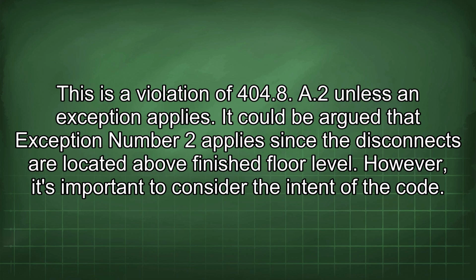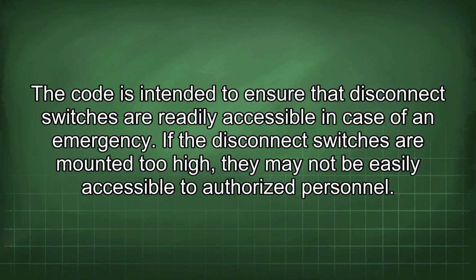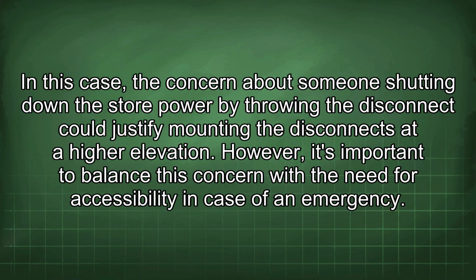However, it's important to consider the intent of the code. The code is intended to ensure that disconnect switches are readily accessible in case of an emergency. If the disconnect switches are mounted too high, they may not be easily accessible to authorized personnel. In this case, the concern about someone shutting down the store power by throwing the disconnect could justify mounting the disconnects at a higher elevation. However, it's important to balance this concern with the need for accessibility in case of an emergency.